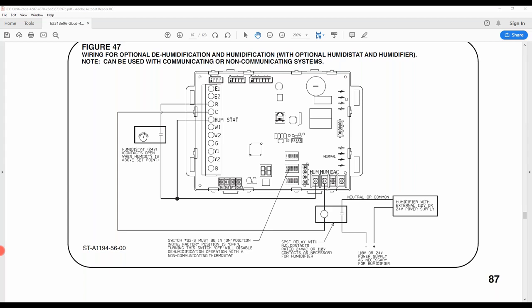Yeah, when you use the EcoNet stat, how do you test that humidity to see if the humidifier is working when you're above 45% humidity in the house? All right, give me one second. So the question is, if you have an EcoNet thermostat, how do you test the humidity? There are a couple different ways they came out with. I believe now they have a test that you can send and test the humidity closing with it. The other option is you're able to raise the humidity setting up to 90 to 99%. Then that'll be able to close those contacts.